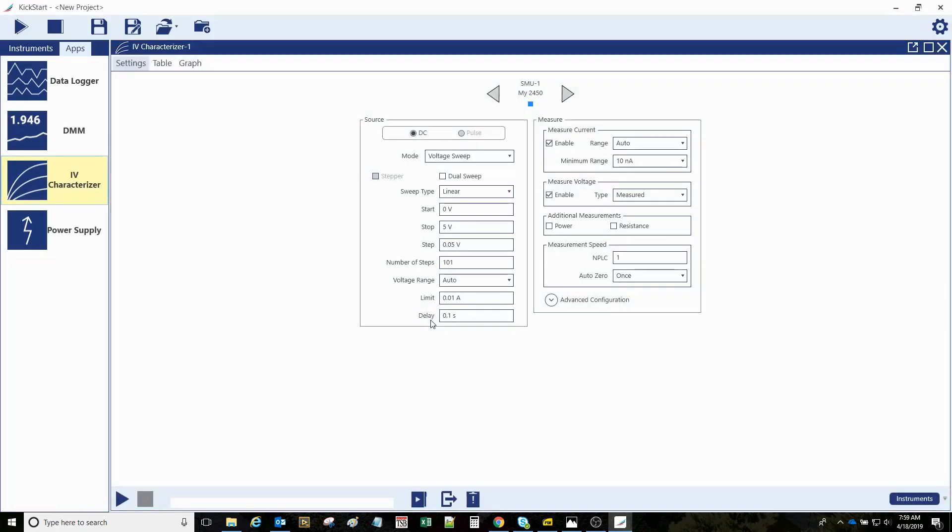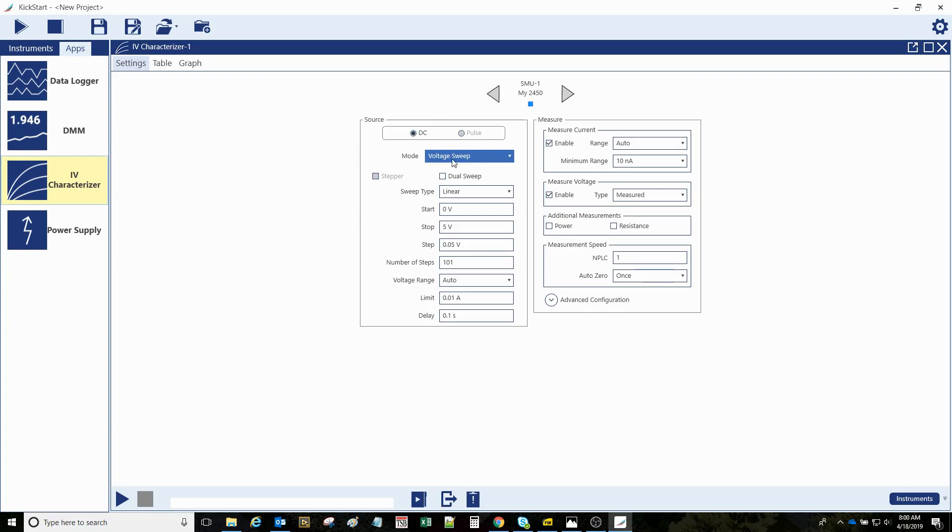In a few moments it gives me a setup screen so I can define what sort of sourcing and measuring actions I want the source meter to perform. For this diode, I'm going to do this default voltage sweep. I'm going to start at zero and only run it up to about 0.8 volts.